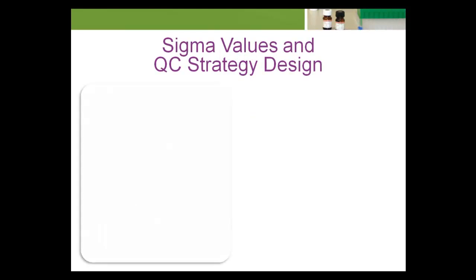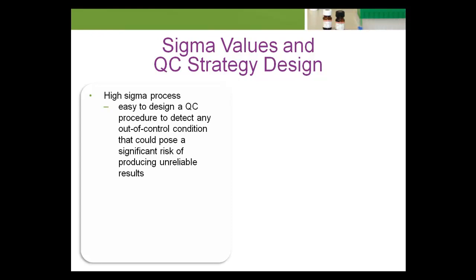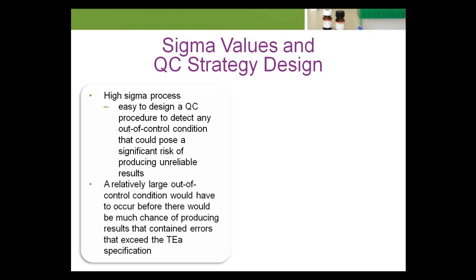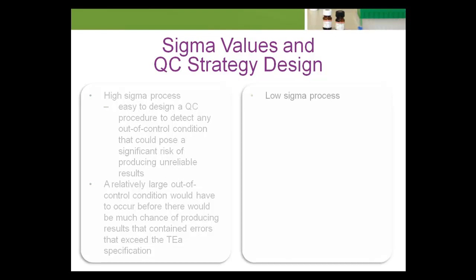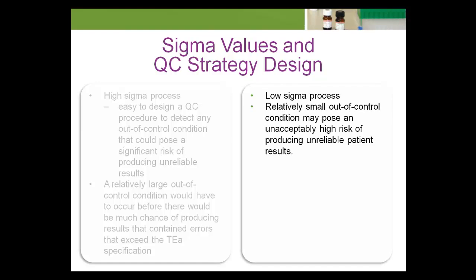Sigma values are useful for guiding QC strategy design. For a high sigma process, it is relatively easy for the laboratory to design a QC procedure to detect any out-of-control condition that could pose a significant risk of producing unreliable results. A relatively large out-of-control condition would have to occur before there would be much chance of producing results that contained errors exceeding the TEA specification. On the other hand, for a low sigma process, a relatively small out-of-control condition may pose an unacceptably high risk of producing unreliable patient results, and it can be challenging to design QC procedures that are good at detecting small out-of-control conditions.